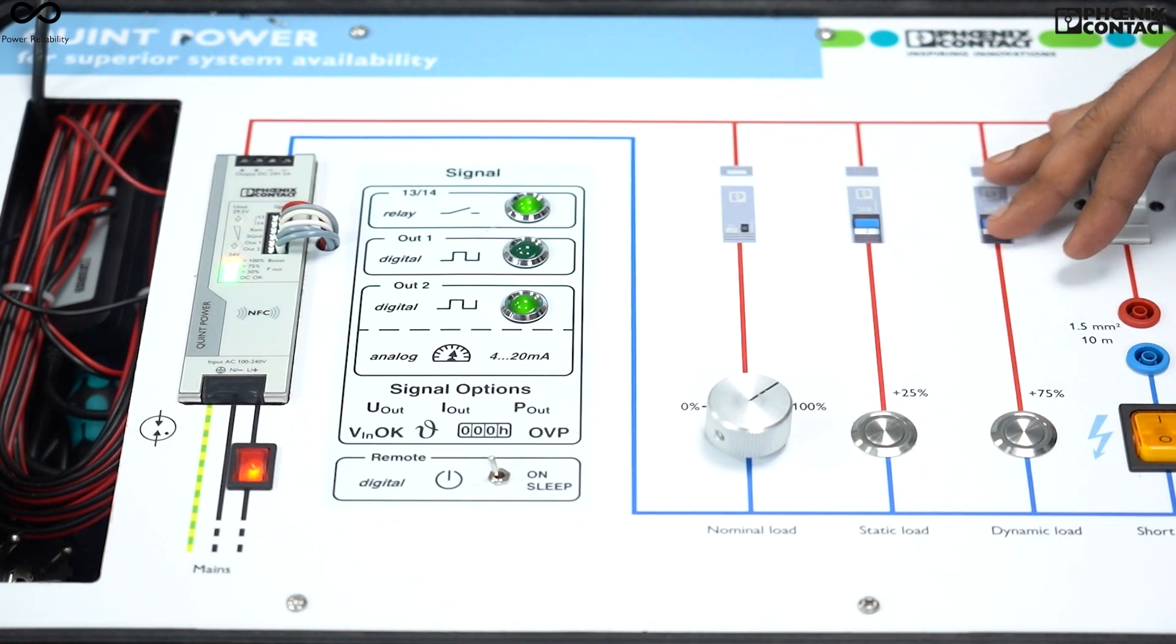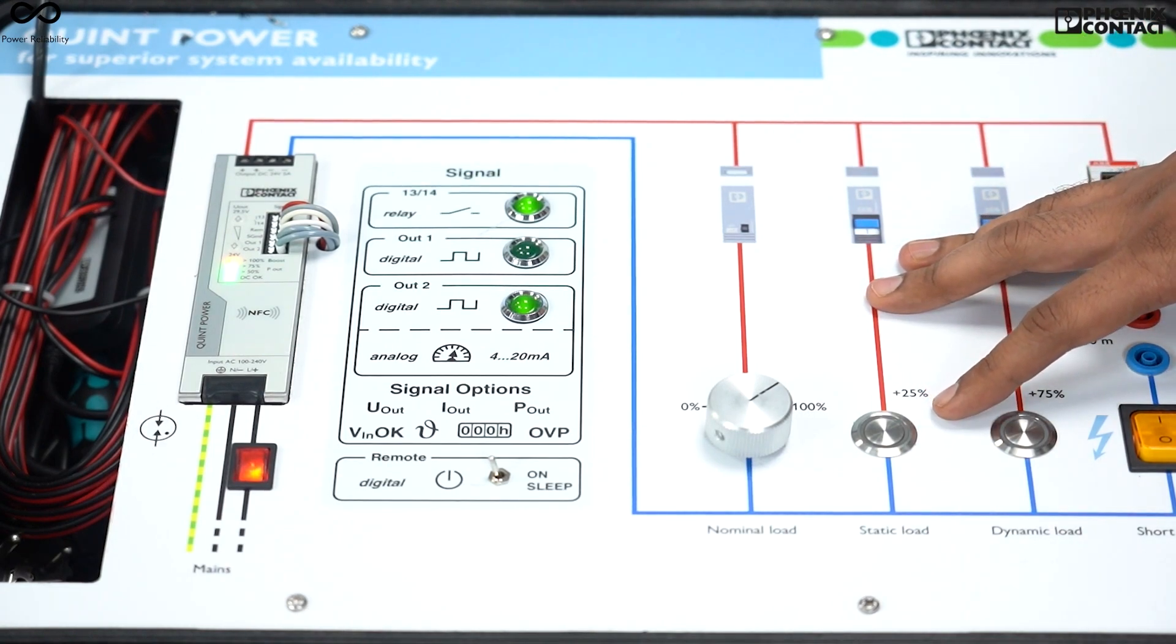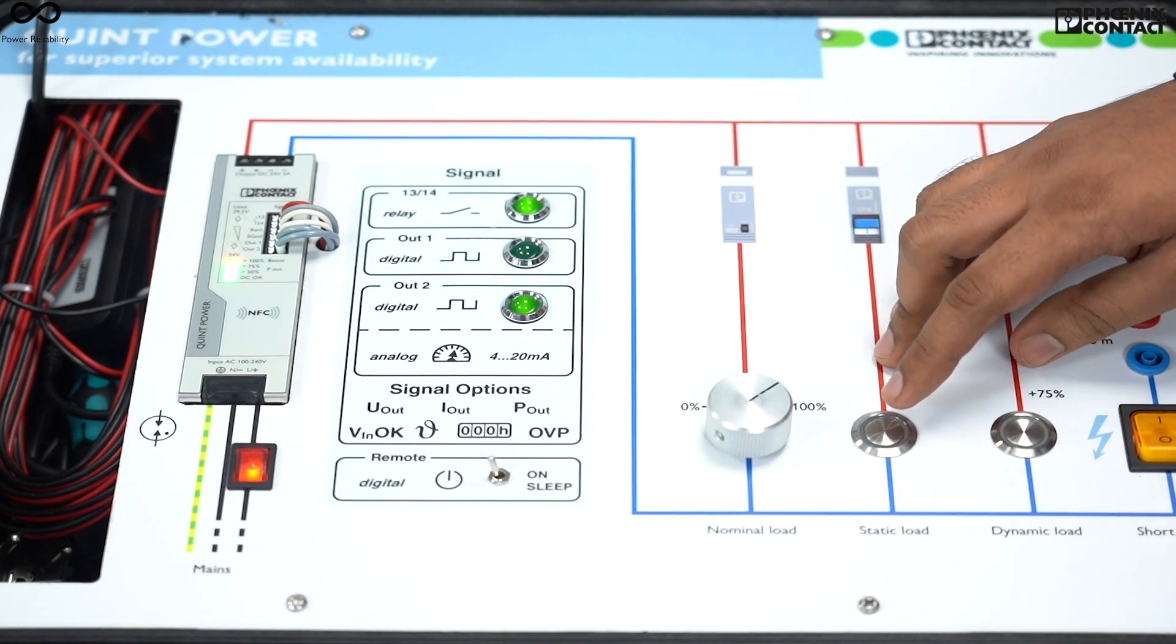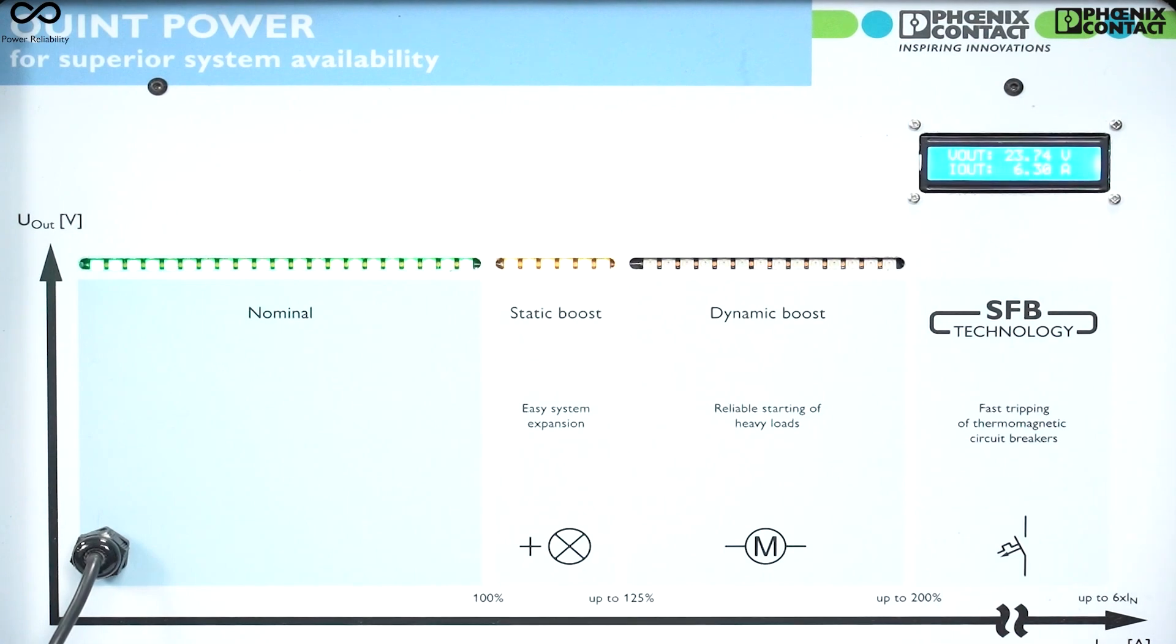If again I increase the load and make the power supply work in static boost mode, I'll press this button static load. This LED indicates that now power supply is working on static boost mode condition and in this boost mode condition it can feed up to 125 percent of its rated value continuously.